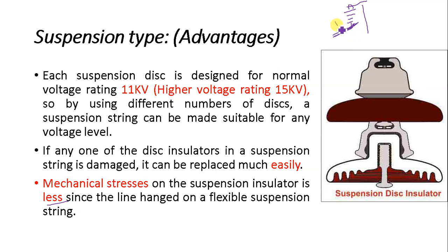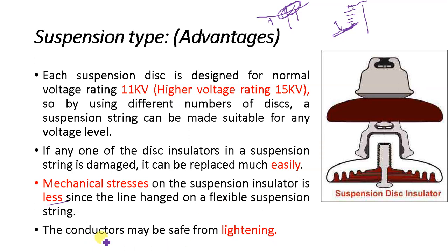A third advantage is that mechanical stress on a suspension insulator is less because the lines are hung on a flexible suspension string. When heavy wind conditions occur, the conductor oscillates and the insulator string oscillates with it, so no significant mechanical stress is imposed on the insulator. In contrast, a pin type insulator is rigidly fixed to the tower and must bear the full mechanical stress from the conductor under high wind. Additionally, conductors in suspension type arrangements may be safer from lightning because the conductor hangs well below the peak of the tower.